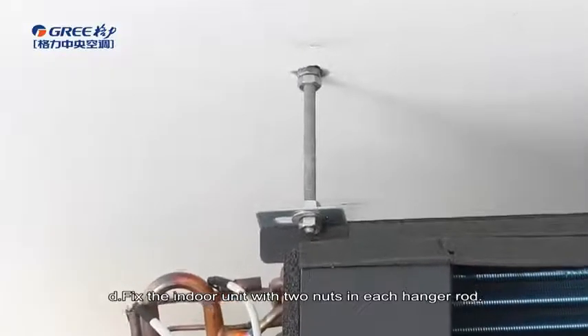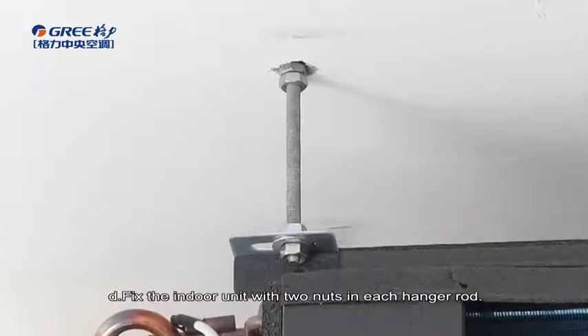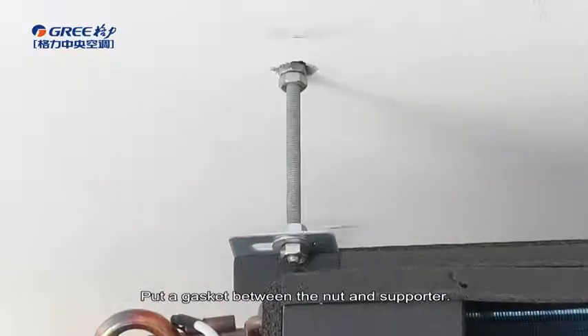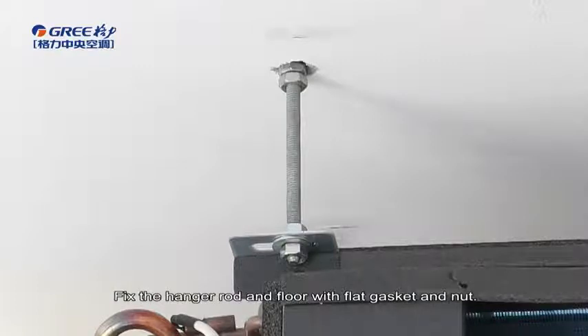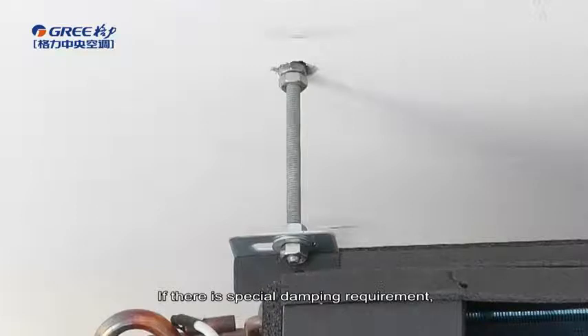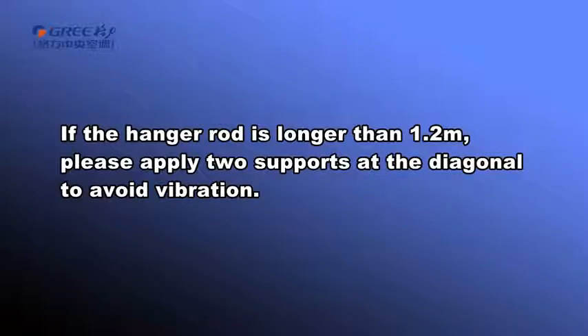D. Fix the indoor unit with 2 nuts in each hanger rod. Put a gasket between the nut and the supporter. Fix the hanger rod and floor with flat gasket and nut. If there is a special damping requirement, please put the damping gasket. If the hanger rod is longer than 1.2 meters, please apply 2 supports at the diagonal to avoid vibration.